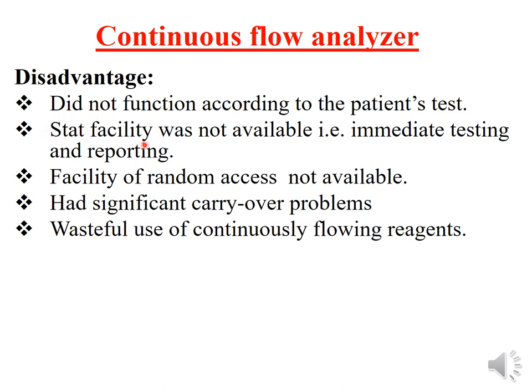The STAT facility allows you to put an emergency sample before other samples if needed, and this facility is not available in continuous flow analyzers. There is no random access available, and there is significant carryover problem despite the bubbles between samples. Due to continuous flow of reagents, there is also a lot of wastage of reagents.